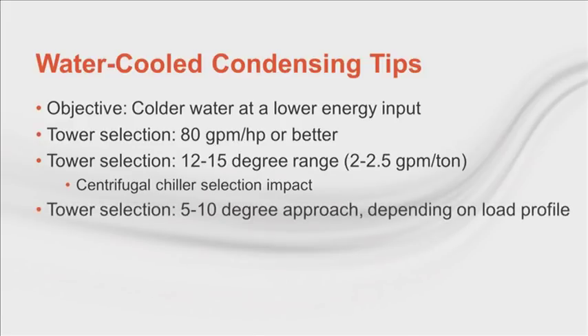Approach gets a lot of attention. This is the difference between the leaving water temperature and the wet bulb temperature. Simply driving for a low approach temperature is not uniformly good across climates and building types. We wrote a newsletter on the topic for a deeper dive on this issue.